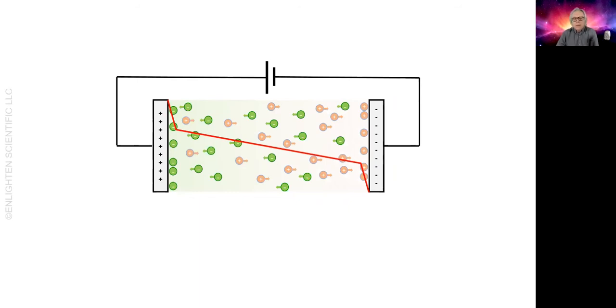So we have underestimation of zeta potential due to electrode polarization, and underestimation due to the wrong choice of model to do the calculation. That's two assumptions that lower the calculated zeta potential. My new instrument can determine what the true electric field is and make a more faithful measurement that will increase your confidence.